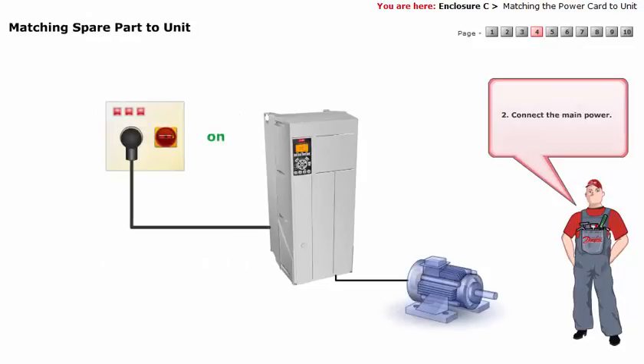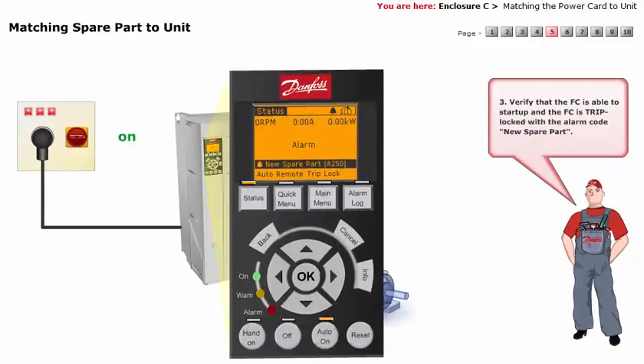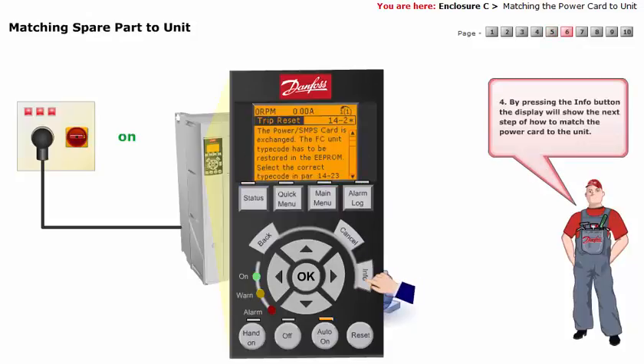Connect the main power. Verify that the frequency converter is able to start up and the frequency converter is trip-locked with the alarm code "New Spare Part". By pressing the info button, the display will show the next step of how to match the power card to the unit.